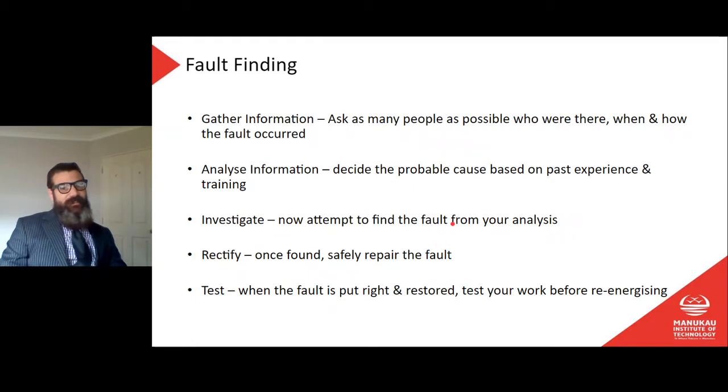All right. Okay, so our fault finding process, and we talked about this in the last fault finding topic with the lighting. So we want to gather information first, ask as many people as possible who were there, when and how the fault occurred. To me, this is a really important one, and I actually don't think that many people do it very well. Working in the fuel industry, and let me outline a little bit about that in terms of what I was doing.